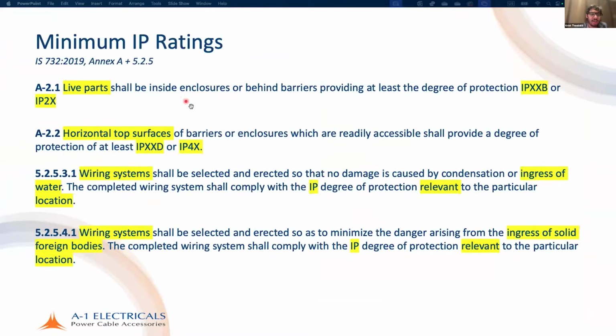Live parts shall be inside enclosures or behind barriers providing at least the degree of protection of IPXXB or IP2X. What are these? I will explain. Basically, if you have any live part inside an enclosure, this is the minimum degree of protection. There are far more stringent requirements for the horizontal top surface, the top of an enclosure, for example. The horizontal top surface of a barrier or enclosure which is readily accessible shall provide at least IPXXD or IP4X. Now, what does this mean? IP2X means that you're providing protection against ingress by a finger, so nobody can touch it. So, for example, an object of 12 millimeter diameter and 80 mm length should not be able to ingress, and any solid foreign body greater than 12.5 millimeters in diameter should not be able to ingress.